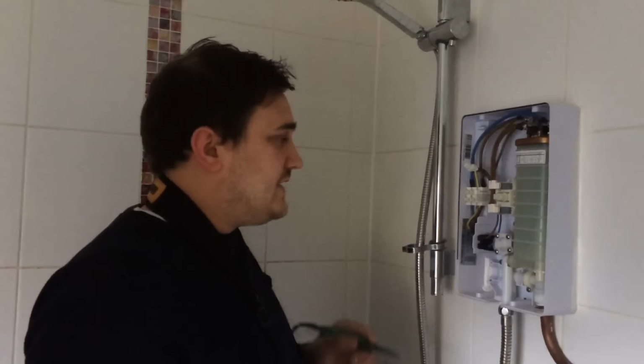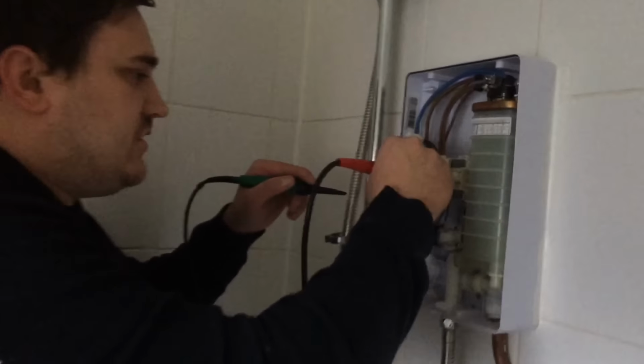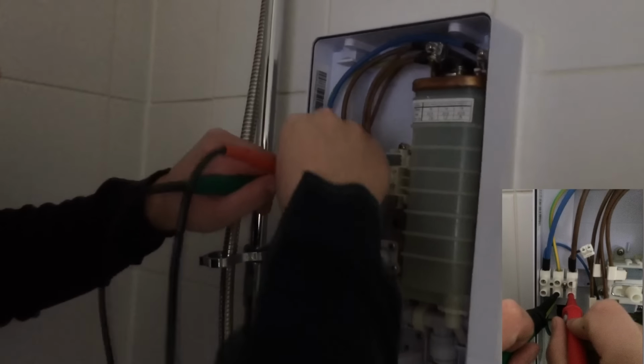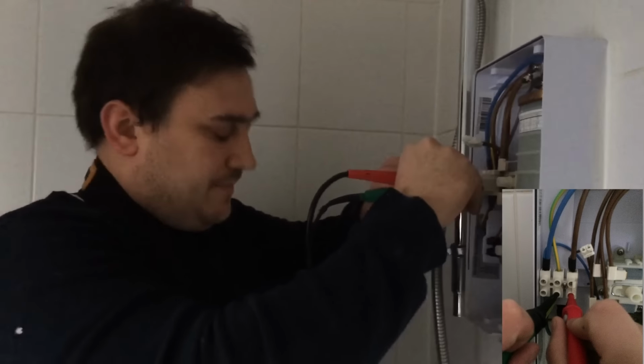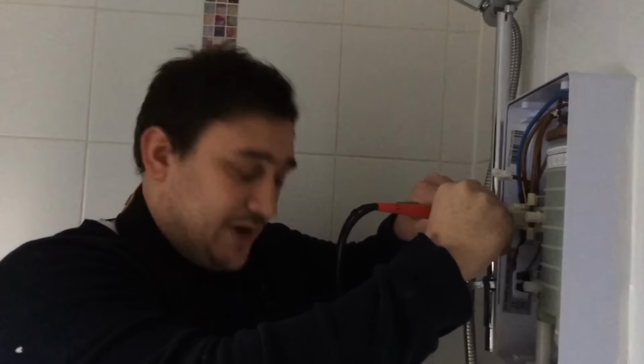Carrying on from the continuity of the CPC, we're now doing the shower circuit. I'm at the shower point. I'm going to probe onto the line and the CPC. I get a reading of 0.09. It is a bit of a low reading, however, the circuit does go straight down. It's not a very long run, a 6mm cable. The resistance in the cable is going to be low. Now the shower switch has been switched. I've proved polarity because I have an infinite reading at my shower.